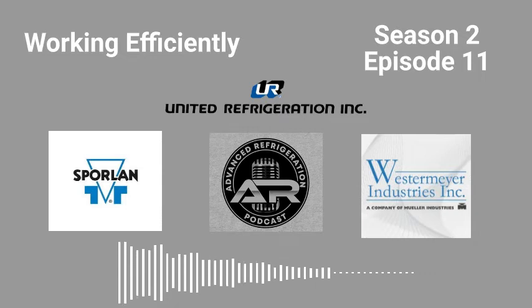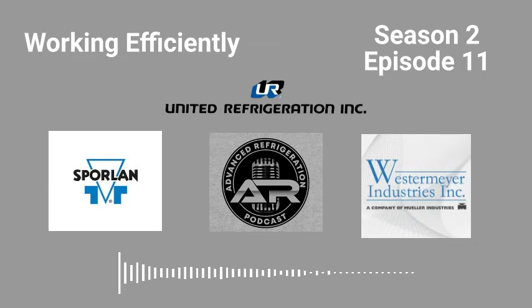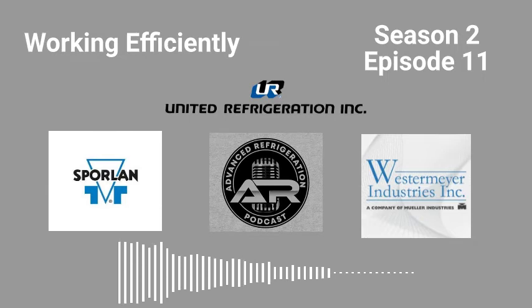Or charging, like Brett said. Dude, I pull the cores in the case. I'm not lugging cans up to the motor room. Let's be honest, I'm lazy, and it's slow. You're going to get hurt eventually carrying jugs up, and it takes double the time. Make them pull a section of the case, and if it's got a hand valve there and a liquid Schrader tap, amazing. Shut the hand valve off and jam it in the liquid line, no throttle, nothing, just let it all rip through the liquid line.